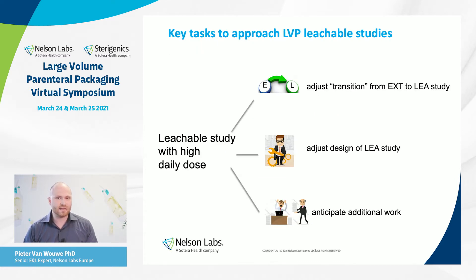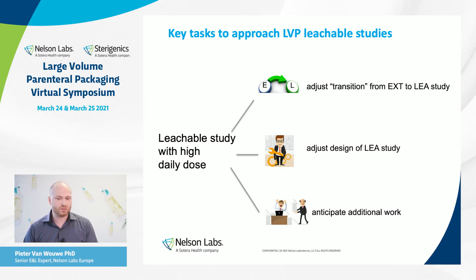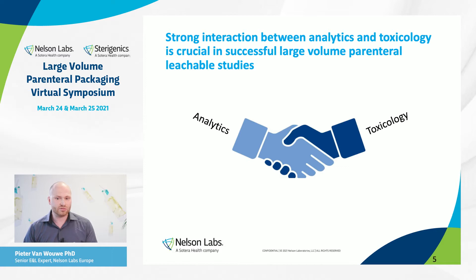As Nelson Labs, we identify three key tasks which we need to address to have a successful leachable study on this type of bag systems. We need to adjust the transition from the extractable to the leachable study, adjust the design of the leachable study, and anticipate potential additional work based on the leachable data. Throughout these three key tasks, there needs to be a strong interaction between analytical work and toxicological data.